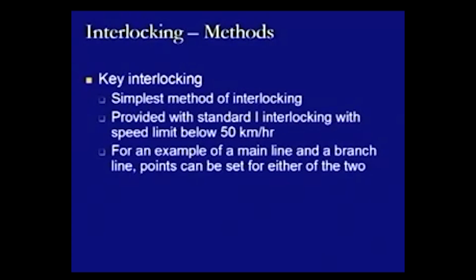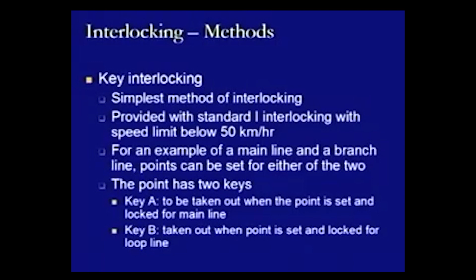For an example of a main line and a branch line, points can be set for either of the two. If we take an example that there is one main line, and from that main line a branch line is coming out, maybe in the form of a turnout, then as soon as there is a turnout, there will be points. So, these points can be set for either of the two conditions. The point has two keys, key A and key B. Key A is to be taken out when the point is set and locked for main line, whereas key B is to be taken out when the point is set and locked for loop line. So, that is the difference between the two keys which are provided at the point location itself. If we are operating the main line, we will be taking out key A. If we are operating the loop line, we will be taking out key B.